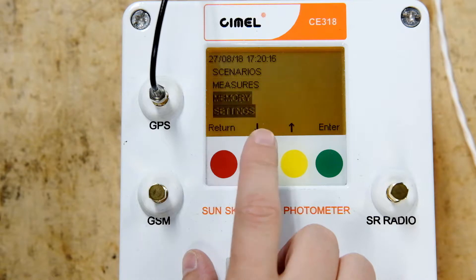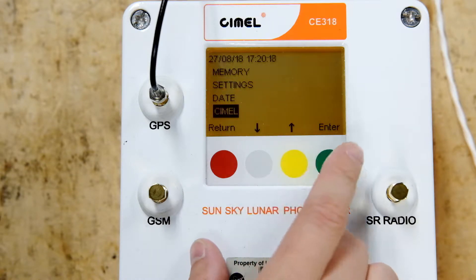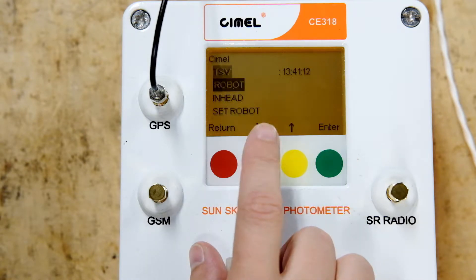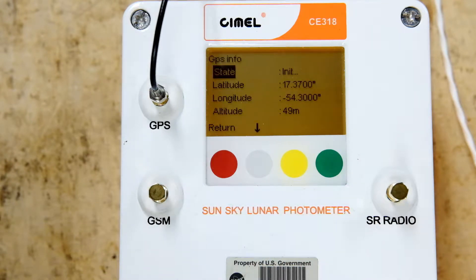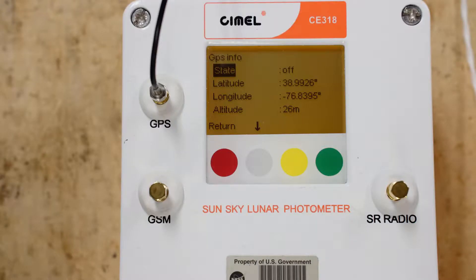Now that the instrument is powered on, we'll update the time and location. Go to the Cimel menu, then scroll down to GPS info. Press enter, then wait three to five minutes while the GPS antenna gets a lock. Once the time and location have successfully updated, state will change from wait GPS to off.